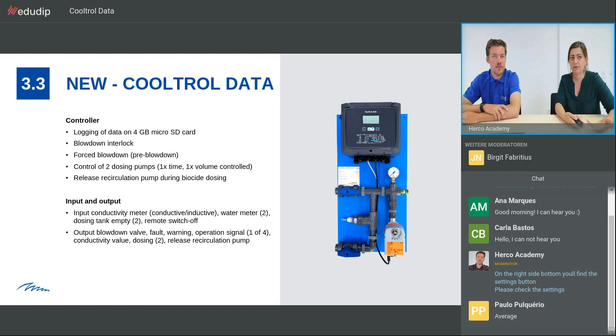We also have the release of the recirculation pump as in the Cooltrol, and we have pretty much similar inputs and outputs, but we have a few more outputs that are quite useful. So instead of only fault, we have here warning and fault. You can program something that is an indication something's wrong, but maybe only the operator needs to know and he has to change something, let's say. Yeah, fill new chemicals in for the dosing pumps. Exactly. And there's the fault, which really means something's really wrong and the system has to be checked. We have additionally also an operation signal. So one of the 4 main functions can be sent out. We'll show that a bit later now.